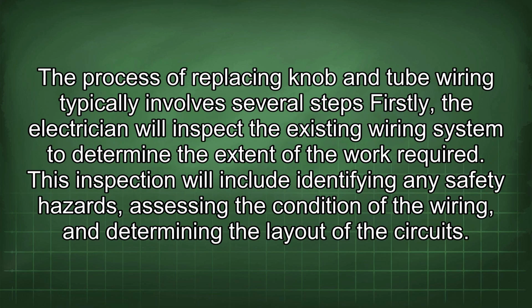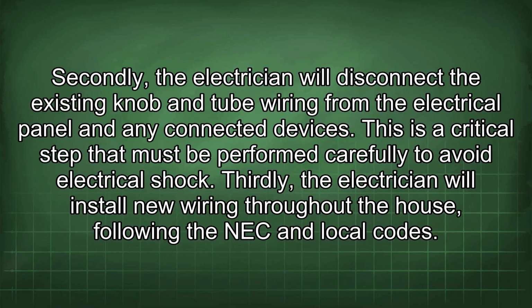The process of replacing knob and tube wiring typically involves several steps. Firstly, the electrician will inspect the existing wiring system to determine the extent of the work required. This inspection will include identifying any safety hazards, assessing the condition of the wiring, and determining the layout of the circuits. Secondly, the electrician will disconnect the existing knob and tube wiring from the electrical panel and any connected devices. This is a critical step that must be performed carefully to avoid electrical shock.